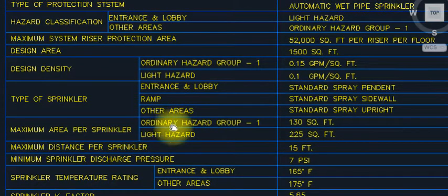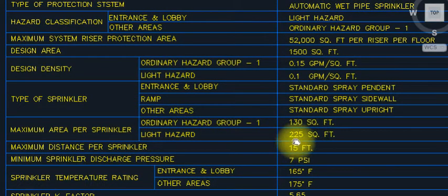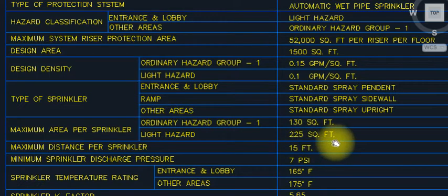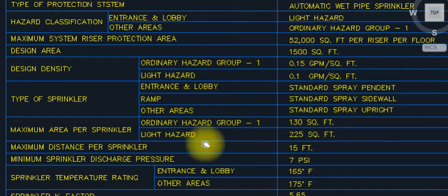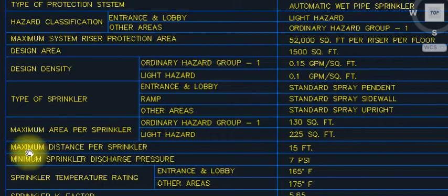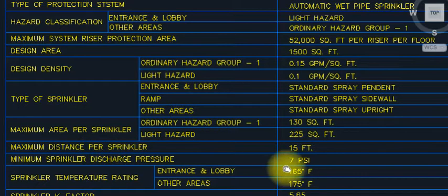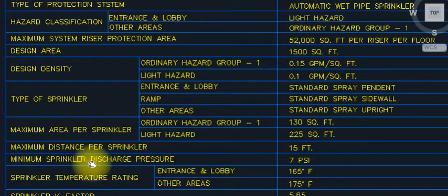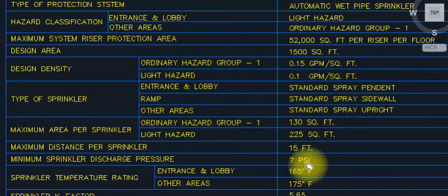Maximum area per sprinkler for ordinary hazard: 130 square feet; and 225 square feet for light hazard. Maximum distance per sprinkler: 15 feet. Minimum sprinkler discharge pressure: 7 PSI.